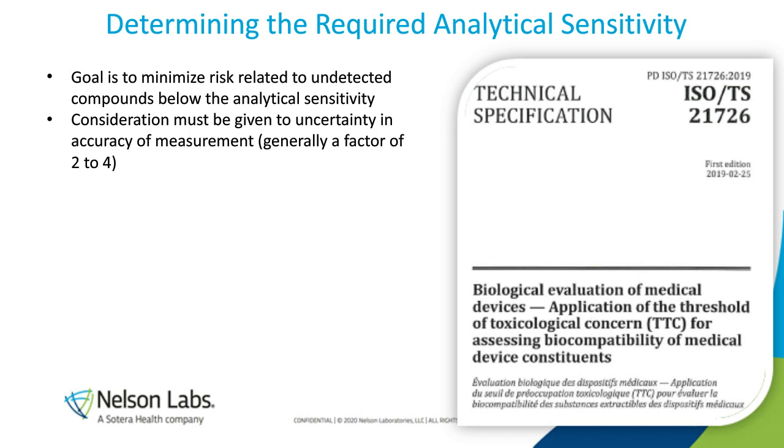We have a relatively new standard that came out in 2019. This is ISO 21726, and it formally applies the idea of the TTC to medical devices so that we can use it to make an analytical evaluation threshold.